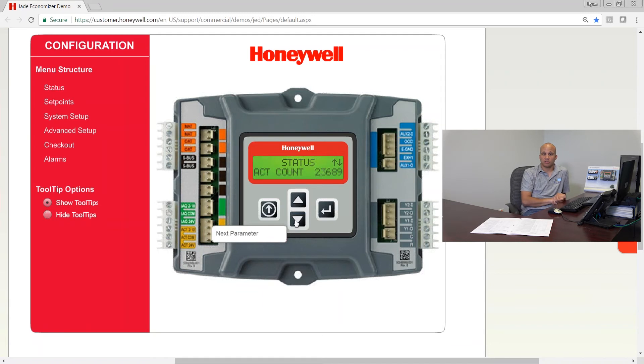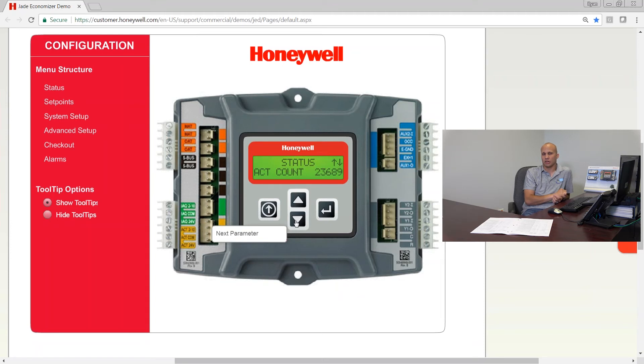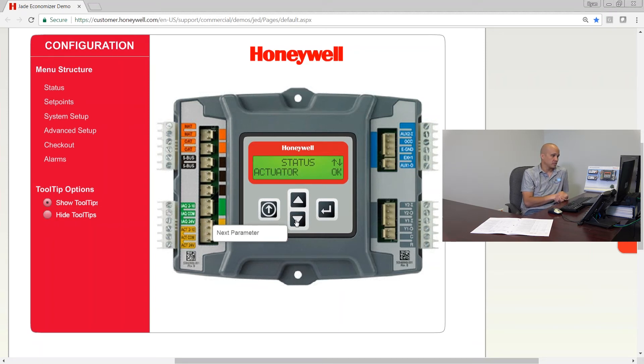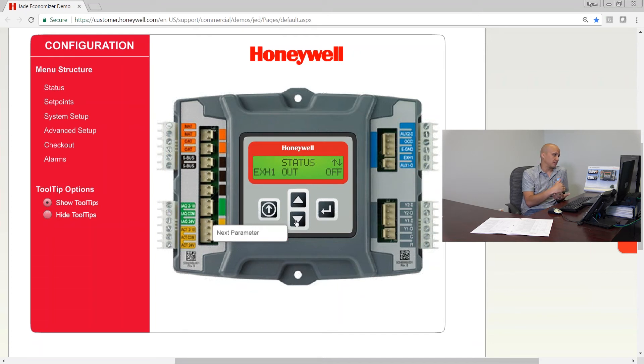If I have a SYLK bus communicating actuator, I also have an actuator count — basically how many times my actuator has cycled. One cycle is 180 degrees of movement total. In this case it's showing 23,000 times. The maximum is 65,000, at which point you're at end-of-life for that actuator and would be looking at replacing it. It's a nice thing to have with communicating actuators so you know how much wear and tear has been put on that motor. The actuator alarm shows okay or alarm — if I have a voltage problem or torque problem on the actuator, it would go into alarm and I'd see that here.